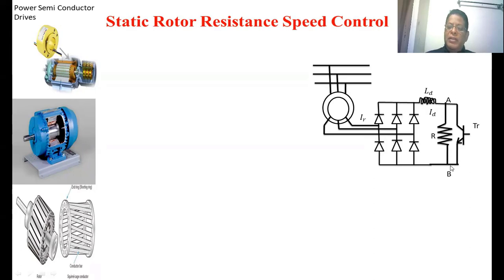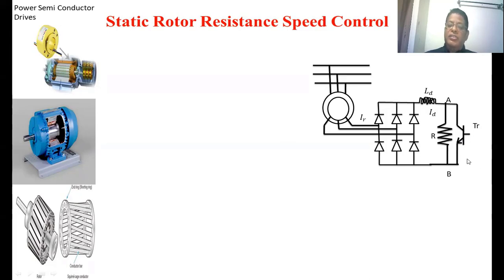The DC power is given to the external resistance between terminals A and B. The resistance between these two terminals is controlled by means of a BJT. Suppose if the BJT is ON, it simply makes a short across the resistance, so the resistance of AB becomes 0. Suppose if the BJT is OFF, then the resistance between A and B is R. By controlling the duty cycle of the BJT, we can control the resistance between 0 and R, smoothly controlling the resistance added into the rotor. This inductor is placed to provide a ripple-free DC link current.